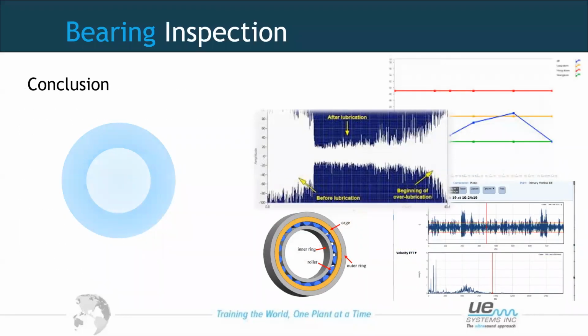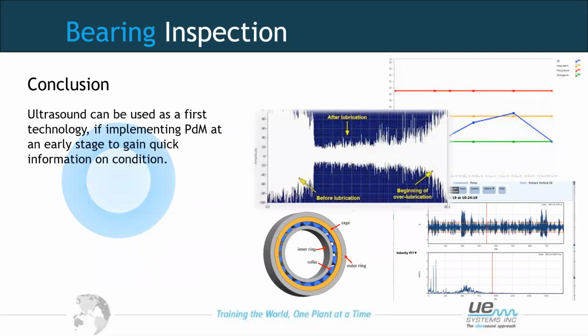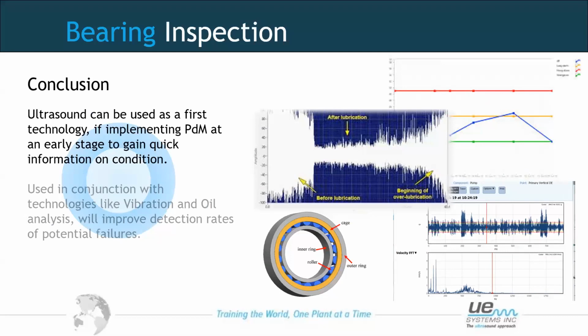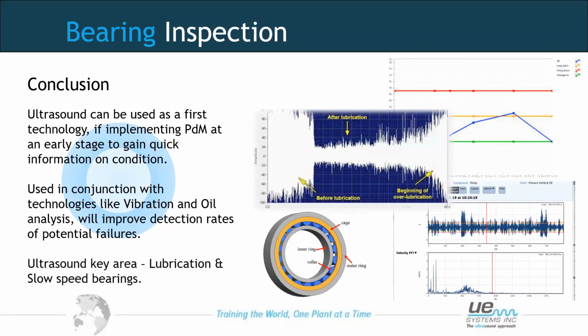So in conclusion to the use of bearing inspections, ultrasound is maybe a good technology to first implement if you have no predictive program on site, to help us gain quick information on the condition, because we're using our senses and it's quite simple to use. And if we use it in conjunction with other technologies like vibration analysis and oil analysis, it will help us improve detection rates of our potential failures. Again, a key area for using ultrasound will be lubrication and slow speed applications. There are some great wins that you can see from that.